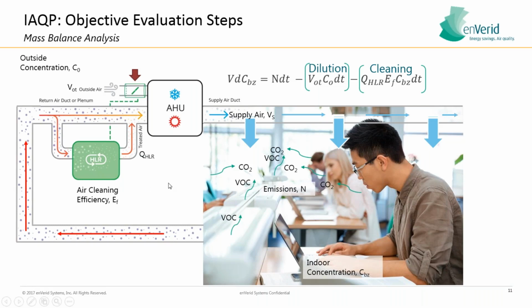This system design is especially useful for retrofit applications. I understand many folks on this call are from ESCOs, but basically what this enables you to do is keep your downstream air handler sizing. If you're using a VRV or VRF downstream, those can all essentially remain constant. And all you're doing is pulling a portion of the return through this device, cleaning it, and then putting that back into the system. So it's built to be self-contained.